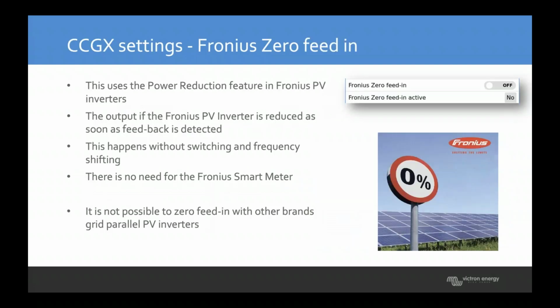There's another option here, the Fronius zero feed-in. If you're connected to the grid, suddenly the Multiplus can't control the frequency anymore because the grid is setting the frequency. In an off-grid system, it can adjust the frequency up and down, but in a grid-connected system it can't. So we have another system in place where we can configure and control the Fronius using this zero feed-in method. It uses the local network to send the message to the Fronius to back off or not. If you require it, that's where you configure that.